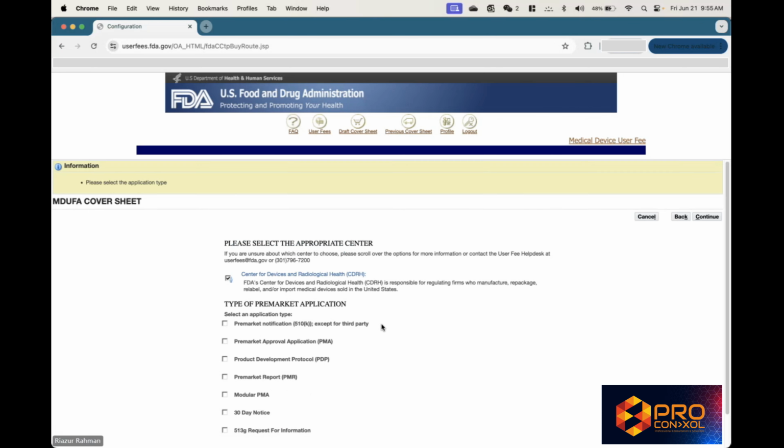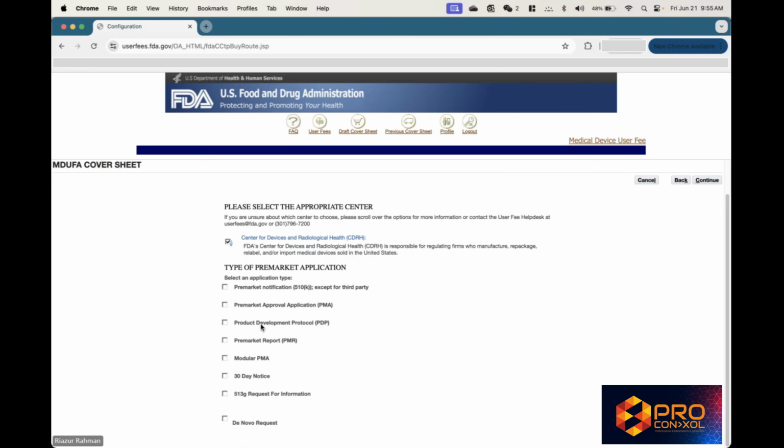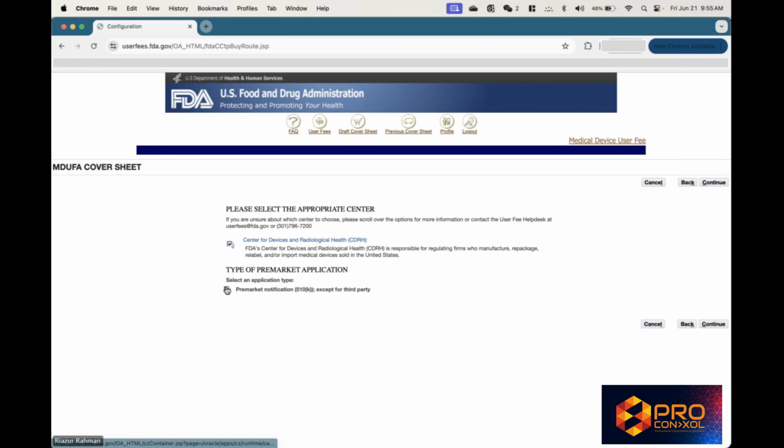Now select the type of pre-market application. There are several types listed: 510(k), PMA, PDP, PMR, modular PMA, 30-day notice, 513(g) request for information, and de novo request. For this video, we will select pre-market notification. Please make sure to select the right category because each submission type has a different fee schedule. And if you mistakenly submit a different fee, then it is very difficult and time-consuming to get the reimbursement from FDA.